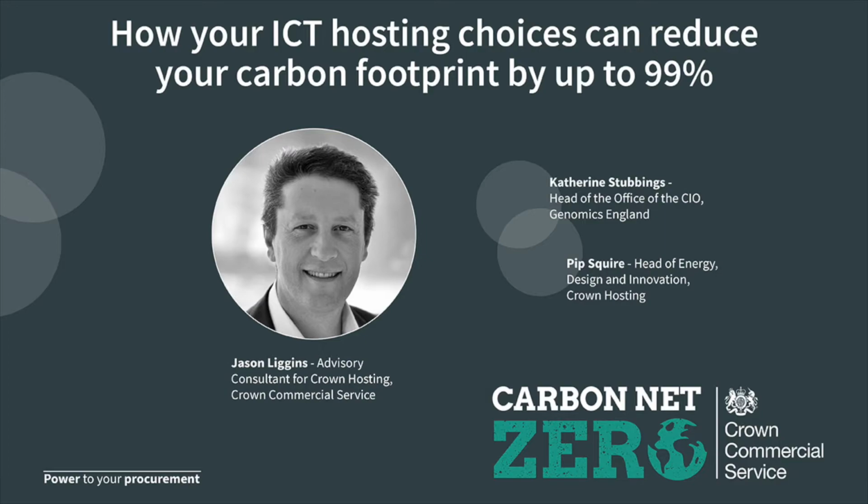A data center itself is typically an aggregation of server rooms, each of which is going to have a capacity of more than 200 kilowatts, probably up to anywhere between 1,000 and 1,500 kilowatts. And these rooms have advanced cooling and ventilation systems to provide the controlled temperature and humidity required for the optimum performance of the IT equipment. They're also very secure, and they will have more than one power supply with backup power generation, and everything is deployed in such a way that the facility has no single point of failure and can undergo maintenance without a loss of service. In other words, you put your server in there and the operator will guarantee the power stays on, the cooling stays on for the duration, 365 days a year.